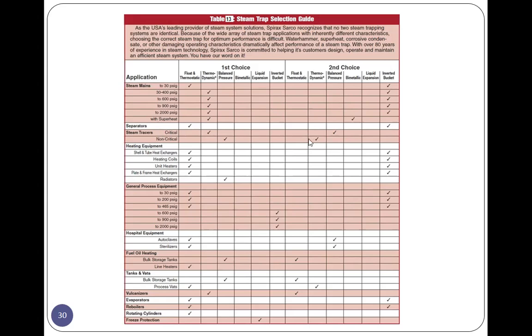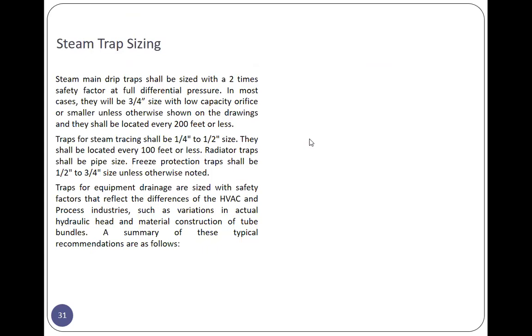Steam trap sizing. Steam main drip traps shall be sized with a 2 times safety factor at full differential pressure. In most cases, they will be 3/4 inch size with a low capacity orifice or smaller unless otherwise shown on the drawing, and these shall be located every 200 feet or less.